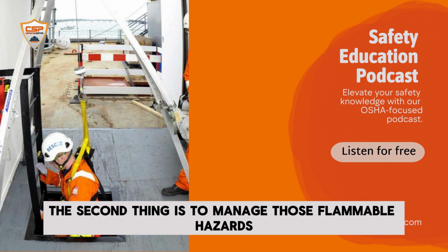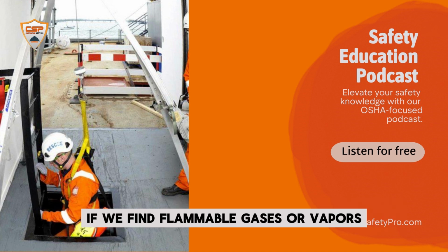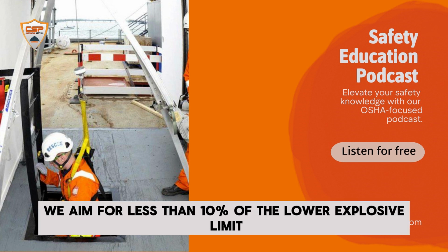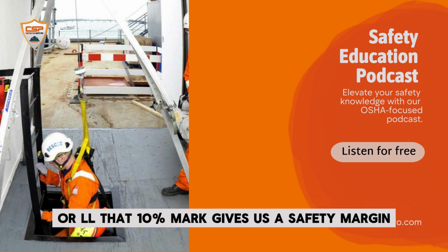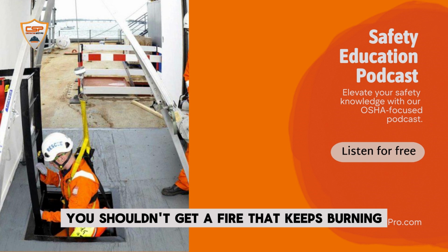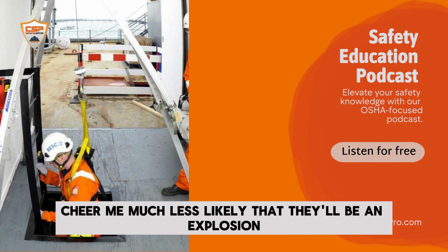The second thing is to manage those flammable hazards. If we find flammable gases or vapors, we use ventilation to dilute them, basically to spread them out so they're below their ignition point. Usually we aim for less than 10% of the lower explosive limit, or LEL. That 10% mark gives us a safety margin. Basically, below that, even if there's a spark, you shouldn't get a fire that keeps burning. So you're making it much less likely that there'll be an explosion.